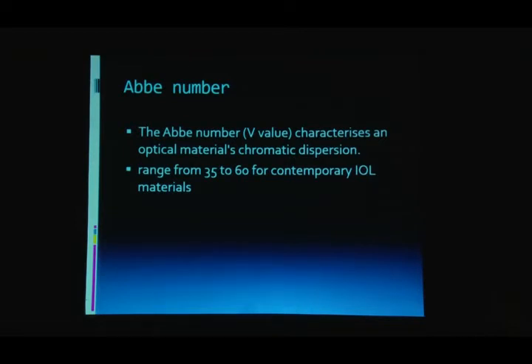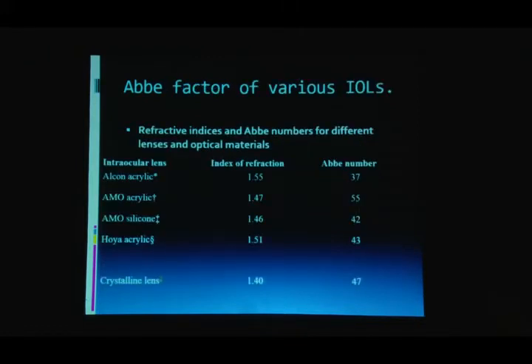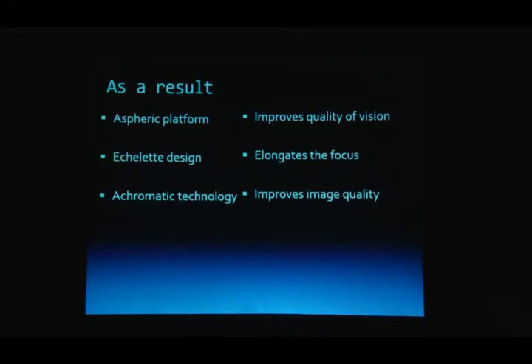The Abbe number measures optical material dispersion — higher means less chromatic dispersion. Available IOL materials range from Abbe numbers of 35–60; most IOLs on the market range from 37–47, while the acrylic from AMO (no financial interest declared) reaches 55. This lens on an aspheric platform with negative spherical aberration of -0.27 and the echelette diffractive design achieves maintained image quality. The modulation transfer function graph demonstrates very good image quality at the retina for this lens.